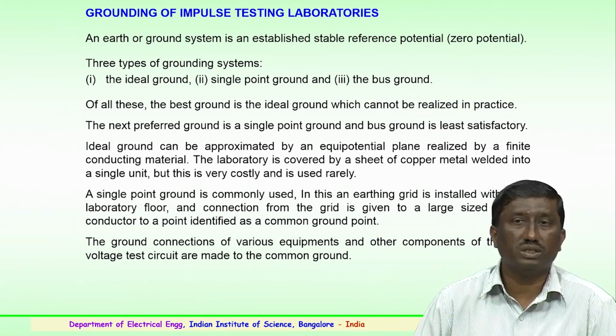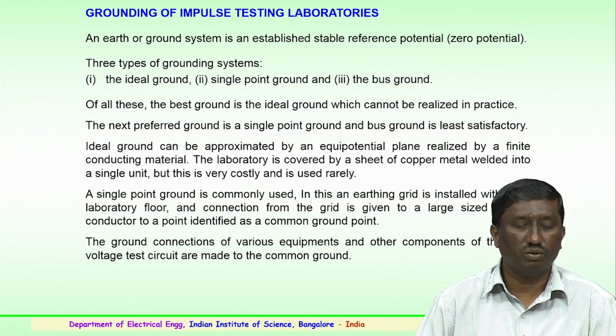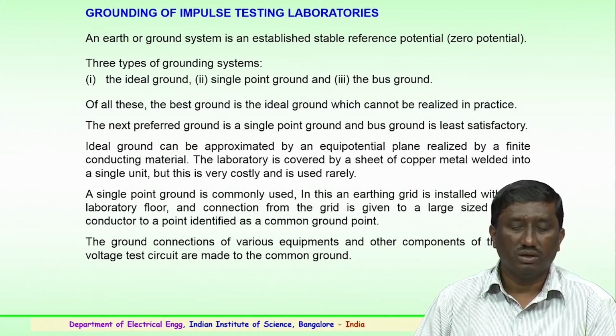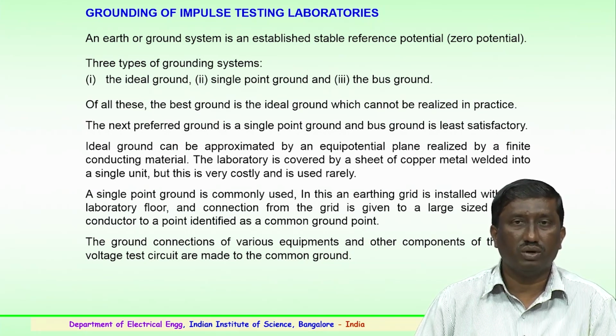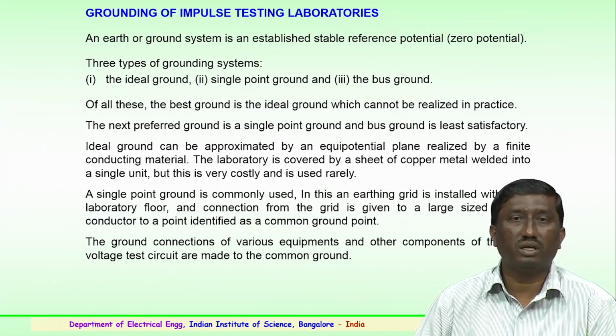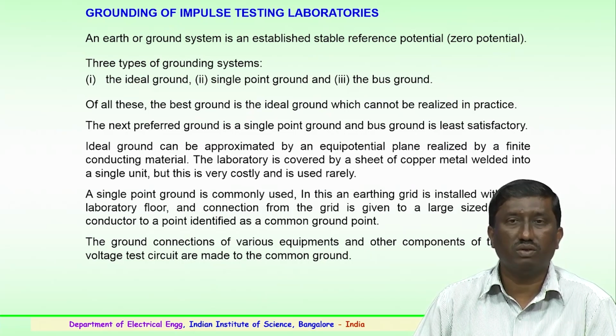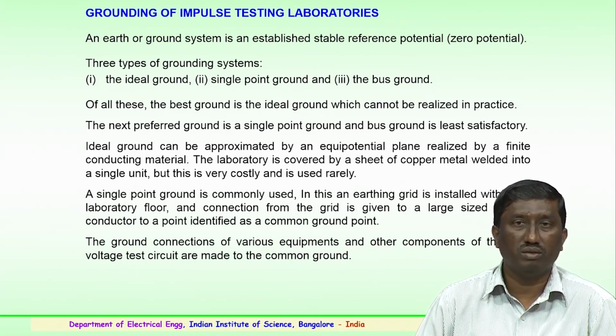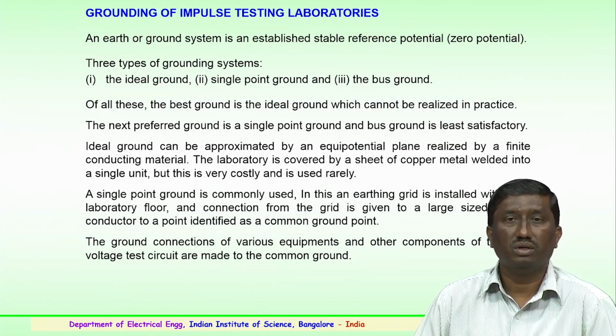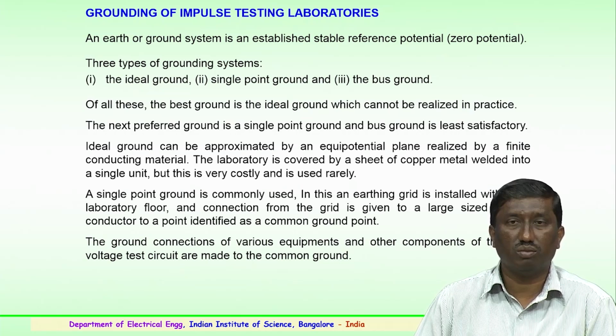So, we have tried to discuss the importance of the planning of the high voltage laboratories for the testing of equipments. The important component being the grounding of the impulse laboratory. In the testing laboratory, this is very important. Here, an earthing or ground system is an established stable reference potential, that is 0 potential, very important to be noted. Three types of grounding systems are normally employed in the impulse testing laboratories. This could be the ideal ground, the second the single point, and the bus ground. These are the three different types of grounding which are normally employed.